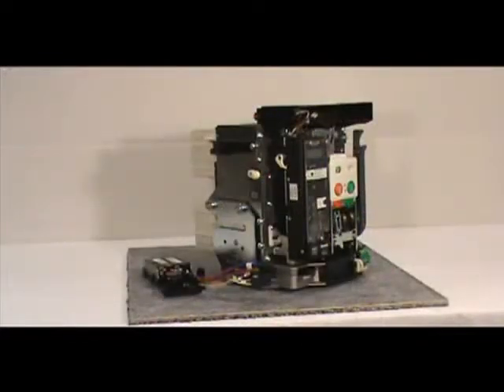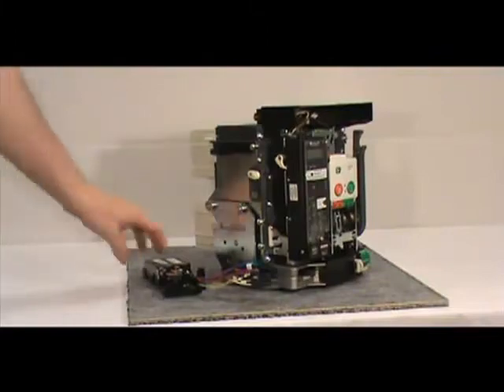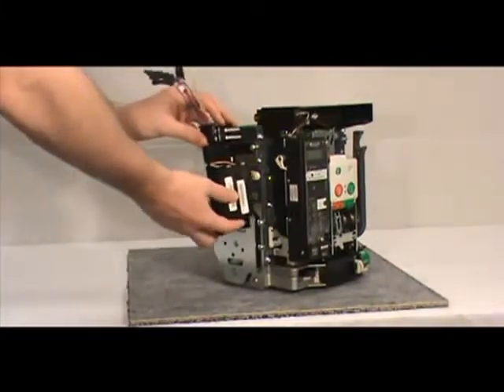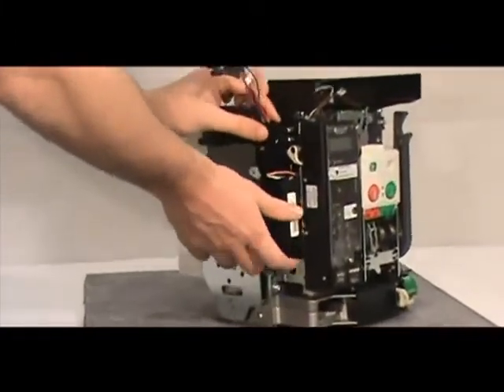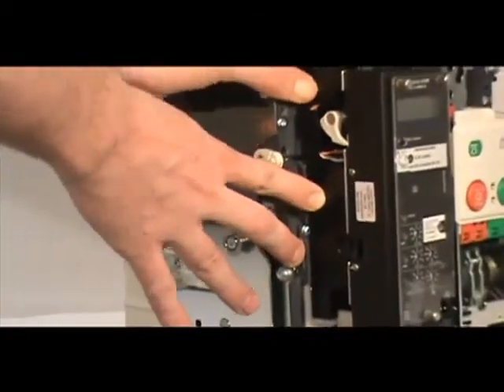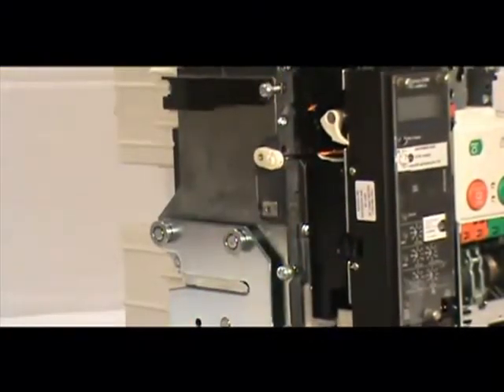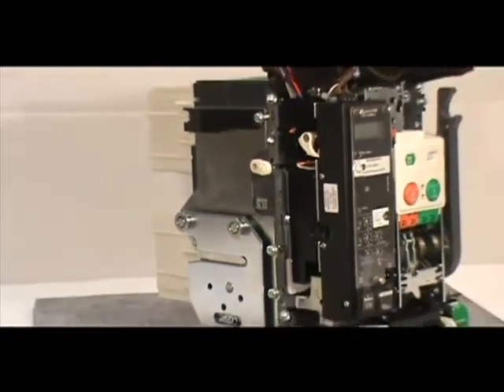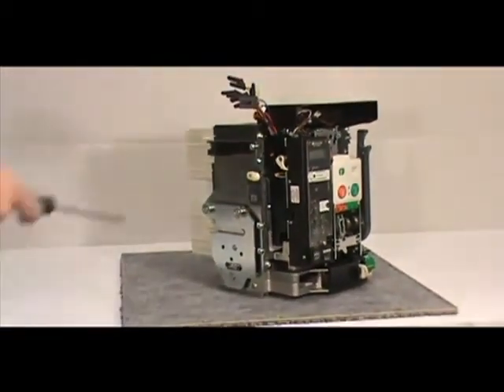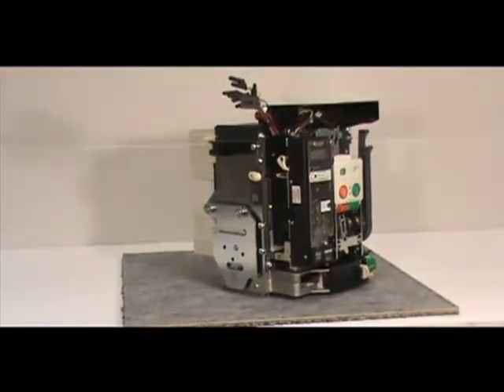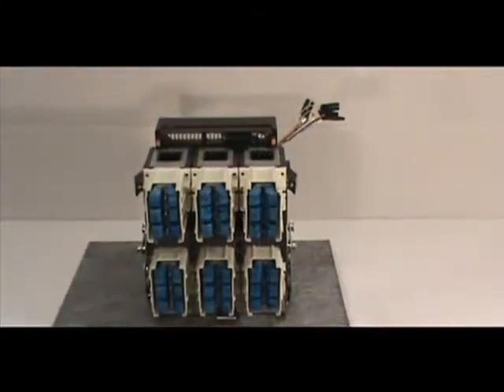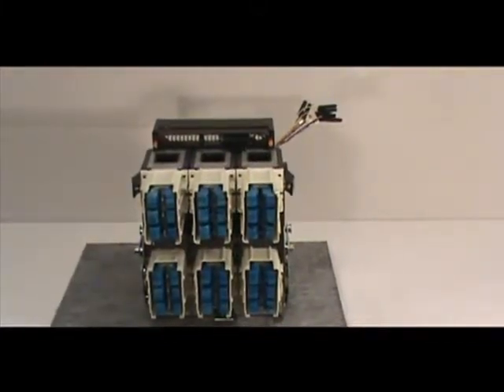After you've secured the UVR, shunt trip, overcurrent trip switches, and routed the secondary leads, place the left accessory tray in its original position. The secondary leads should extend out from behind the trip unit once the left accessory tray is installed. Now that the left accessory tray is installed, you can make the appropriate secondary connections.